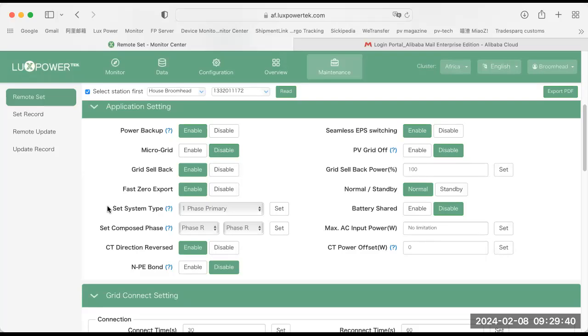The EPS plug doesn't fit into the AC in, and the AC in or the grid supply doesn't fit into the EPS plug. So once you read the top here and you connect your wires inside correctly, it's simply a matter of putting the plug right in here. And then from a serviceability point of view, if you need to do any maintenance on the machine or do any changes, it's very quick. As a matter of fact, we've timed it where we can get the machine changed within 20 minutes. Not that the LXP5 ever needs to be changed. It's one of the most robust machines.